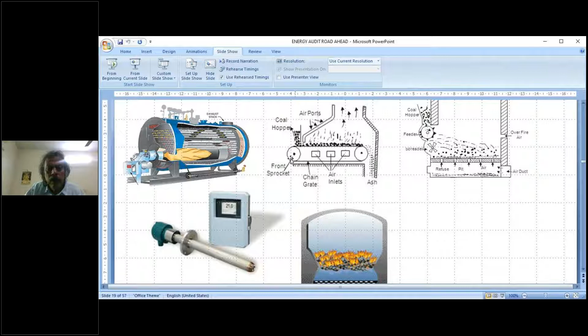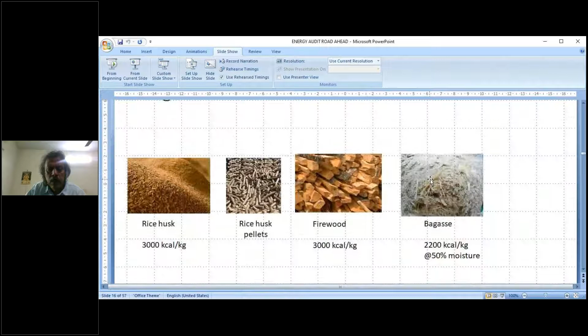Then you also look into the unburns. When you audit a boiler, typically what we do is take the boiler, look at the fuel fired, the total input in kilocalories, and the total output from steam, the total heat in steam. Heat in steam divided by heat in fuel gives the efficiency of the boiler.